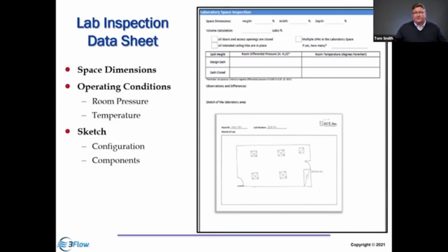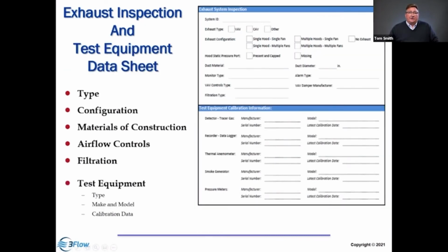We think it's important to sketch the space because things can change. The data that you collect is only as of that time and date tested. If they put a new wall in or move a diffuser or put a new piece of equipment, that could influence the test results. So we want to have the conditions recorded under which we conducted the test, so that we have a record of the performance at that time, and that sets the benchmark for the operation at that moment in time.